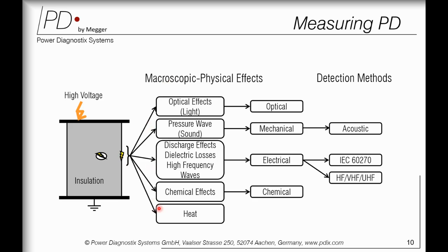Energy can be in different forms. It can be optical lights, pressure waves, discharge effects, dielectric losses, high frequency waves, chemical effects, and heat. So when you have different types of energy, you have different methods, or techniques, to capture them. We typically use optical for optical lights, mechanical for pressure waves, electrical for high frequency, dielectric losses and discharge effects, and chemical for the chemical effects. But when you talk about partial discharge on the GIS, UHF and acoustic are the most widely used techniques, especially on site. We will now discuss both technologies one by one in upcoming slides.